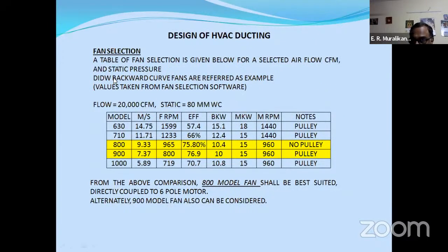Now, fan selection. See, here is where the fan selection happens. Now, for example, say we have a 20,000 CFM fan and static 80 mm. Okay. Now, how to select the fan? If you have fan selection software with you, fine, or you can demand from the fan supplier, Kruger or XYZ, or the AHU's fan supplier, to submit their fan selection with different model options. So here, for 20,000 CFM and this static, we have multiple models: 630, 710, 800, 900, 1000.